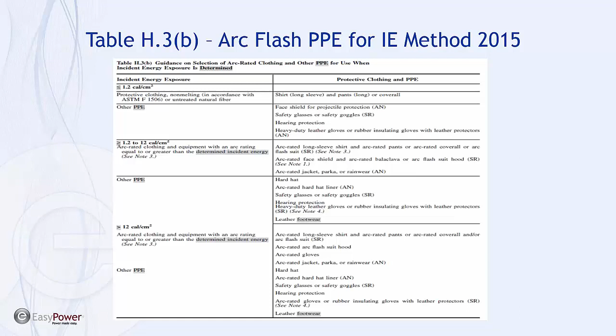Now here's the point where it all comes together in the standard itself. So we're referring to Table H3B, and that's the guidance on the selection of arc-rated clothing or other PPE when we have calculated incident energy. There's 3 ranges, and we're able to calculate and suit up to that specific incident energy that we've predicted. You'll notice that there are no categories indicated, but the focus is on the material and people understanding that some parts of the body may be farther or closer to the arc source in a worst case situation, and it's encouraged that even though we have maybe a minimal level of suiting, that if we have body parts that are inside that distance, that they may, based upon the assessment of the worker, frankly, and the manager involved, require additional protection.